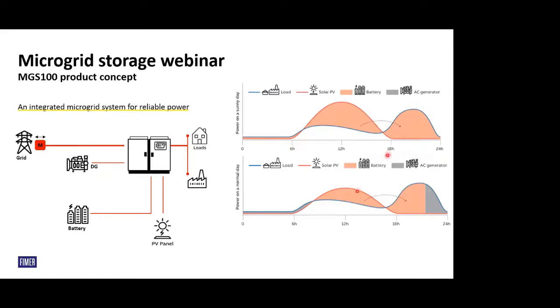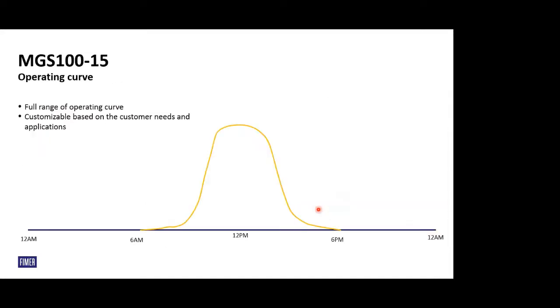Let's say it was cloudy or raining in the monsoon time when the generation is on the lower side, what you generate would not be sufficient. After the battery discharges to a set point, the generators will be turned on automatically by the microgrid system, usually a diesel generator or sometimes a biomass generator, and the night loads will be catered by the diesel generator in that case, or the biomass generator.